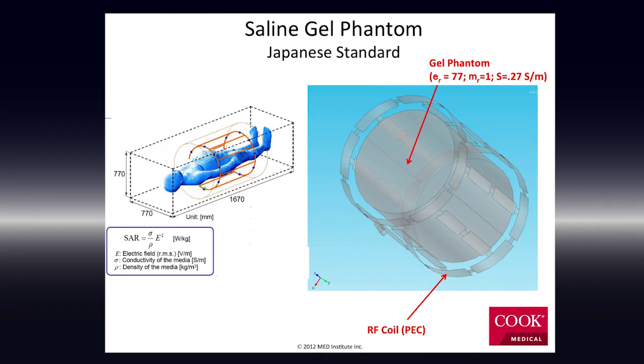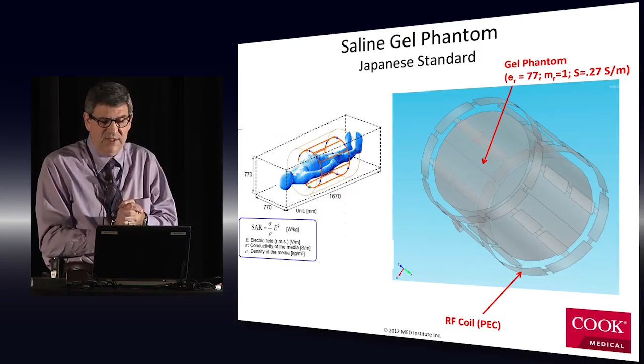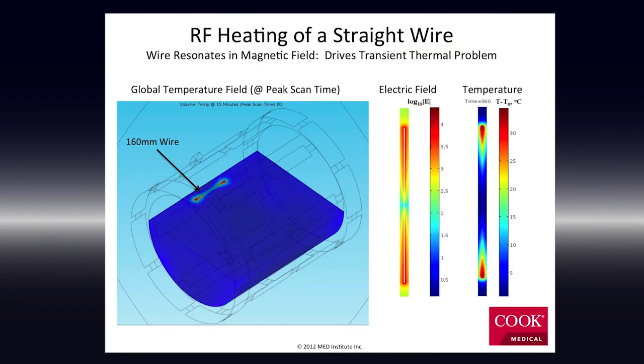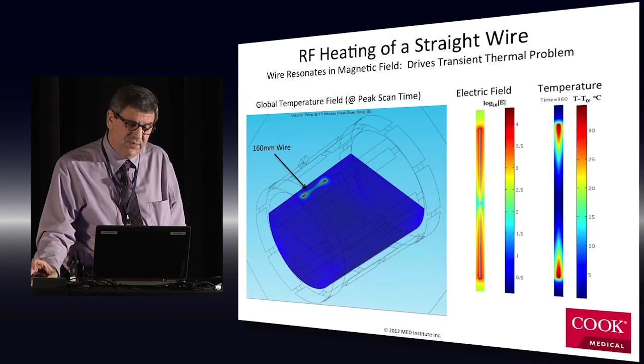Next thing we do, and this is all part of the validation, is to bring a phantom in, just what I showed earlier. This is a Japanese standard. It's a round gel phantom. It has human tissue properties as far as its dielectric and electrical conductivity and its thermal conductivity. We put a round phantom in, and there's some literature with this round phantom where people have made measurements. So if we put a wire into this RF coil and we drive it at the right frequency, for 1.5 Tesla, it's approximately 64 megahertz. Sure enough, it resonates. You get electric fields scattering off of the tips of the wire, and you couple the physics, and you get high temperatures at the end of the wire.